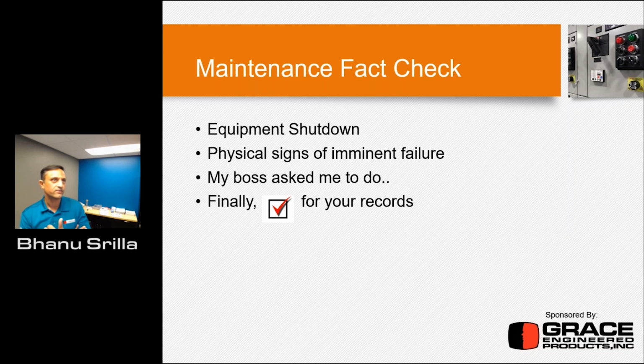And then the second reason is whenever there are physical signs of imminent failure, like if you see a hot spot, or arcing or a flashover inside the cabinet that you can visually see, or any kind of temperature rise on the equipment, then you send someone to go and perform the task, right? And the last two are pretty common. I do this maintenance task because my boss asked me to, or I have procedures or policies in place which demand that I do the task, right? And lastly, I just do it as a checkbox for the records.